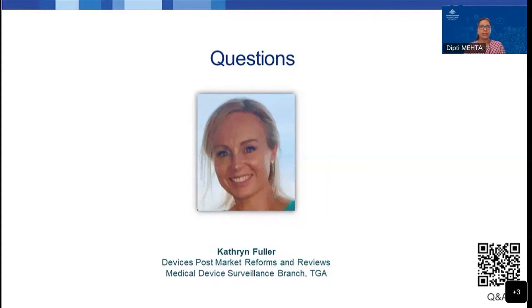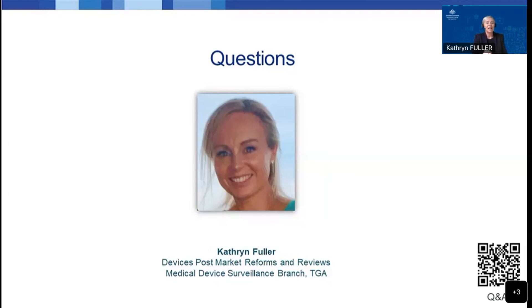The next question is: can you confirm that the CTS portal is not where the TGA would send a sponsor a Section 41JA letter for current medical device applications? So we have the post market review database and the consent to supply database. If the Section 41JA is related to a device that is part of a current approved consent application, it will be sent through the CTS database. If it is for a different ARTG that is not part of an approved consent application, it will be sent through the normal PMR dashboard. They are built in the same way, so there is familiarity - it depends on whether the ARTG is part of the approved consent application.